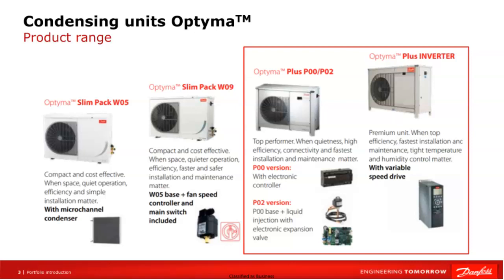The next unit, third from the left, is a premium device, Optyma Plus. It has a completely soundproof housing and full automation, such as controller, pressure transducers, temperature sensor, and displays. Thanks to this, you can achieve a very high efficiency and precisely regulate its operation. It is also possible to connect the unit to the monitoring system, and the installation and commissioning process is much simpler and safer. Optyma Plus units are available in two versions, P00 and P02. The P02 version is a low temperature unit and equipped with a controller and an electronic valve for liquid injection, which enables operation at a very low evaporation temperatures.